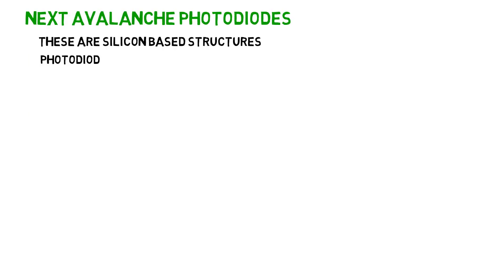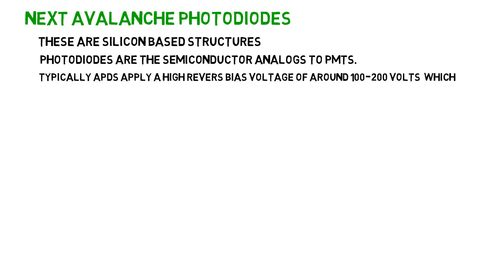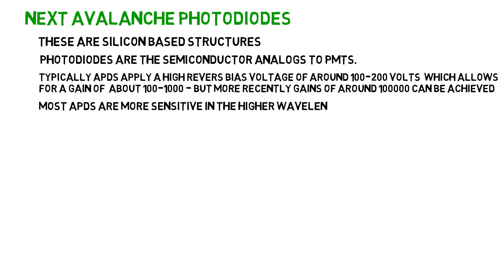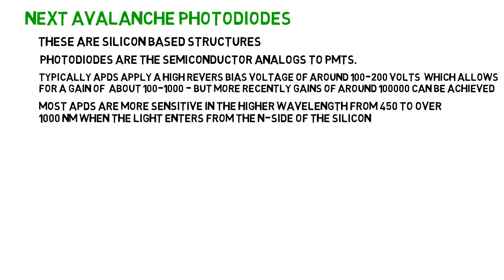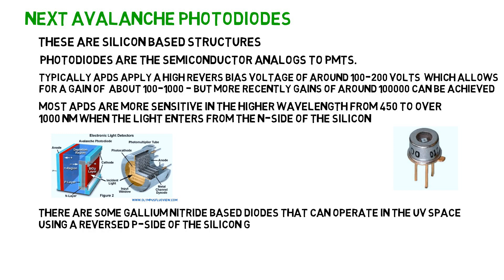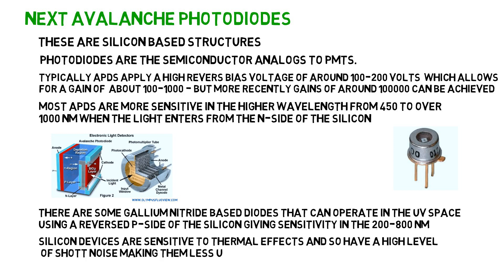Avalanche photodiodes are silicon-based structures and are the semiconductor analogues to PMTs. Typically, APDs apply a high reverse bias voltage of around 100 to 200 volts, which allows for a gain of about 100 to 1,000. But more recently, gains of around 100,000 can be achieved. Most APDs are more sensitive in the higher wavelengths from 450 to over 1,000 nanometers when the light enters from the N-side of the silicon. There are some gallium nitride-based diodes that can operate in the UV space, giving sensitivity in the 200 to 800 nanometer range. Silicon devices are sensitive to thermal effects and so they have a high level of shot noise, making them less useful in very low noise applications.